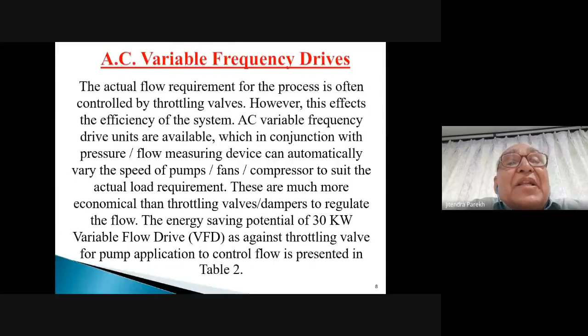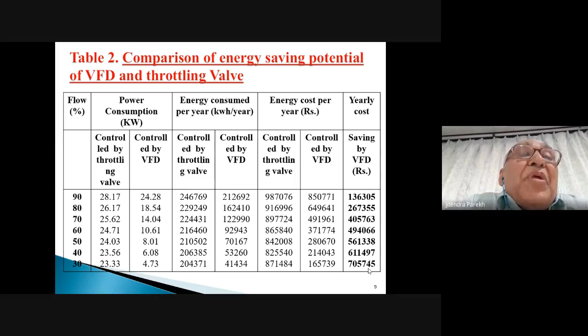Next slide, please. Here you can see on the left hand side, when reducing the plant or pump capacity from 90% downward by throttling, there is a lot of energy saving with the VFD compared to throttling valves. So we recommend that we should use more VFD type of operations, which can be easily operated. On the right hand side, in the last column, there is a lot of saving in terms of rupees also. VFDs have a lot of other advantages when you want to control the flow. So we recommend VFD type operations, which can be connected online, compared to the throttling ones. Next, please.